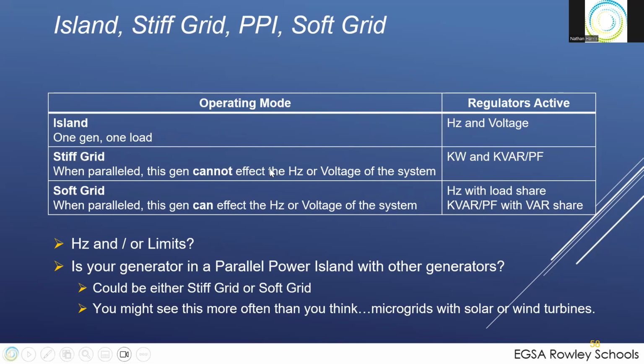We have a stiff grid, and that is if we're pushing our generator up against the grid. In the US, most of it is a stiff grid, and that means your generator is not going to push the grid around. A soft grid is where you have two generators the same size and you parallel them, and one can push the other around. If you increase fuel to Gen 1, Gen 2 is either going to try to decrease fuel, or it may push back on it and go to inverse power if it's trying to regulate speed. So there's a soft grid and a stiff grid, and that's an important discussion you've got to have when you're thinking of your control system.